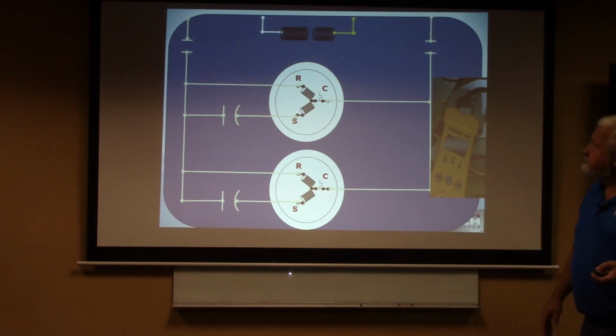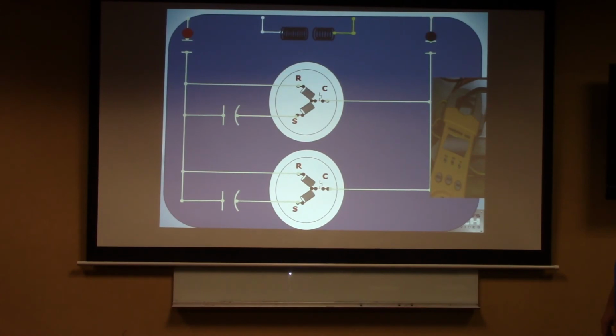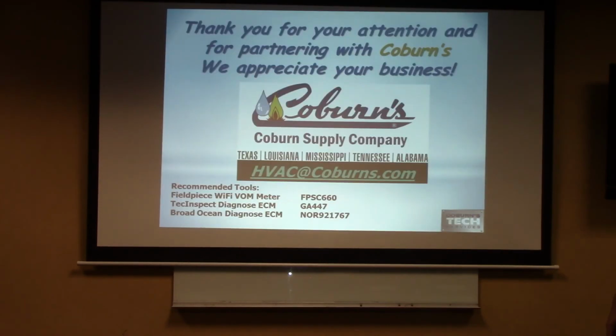Well guys, what are we going to read here? Here and here. The contactor coil is burned, is that right? So what am I going to read there? Still at 240, is that right? So what do I read here and here? 0. So what do I read here and here? 24 volts. If I have 24 volts to the load and the load doesn't work, bad load, absolutely.